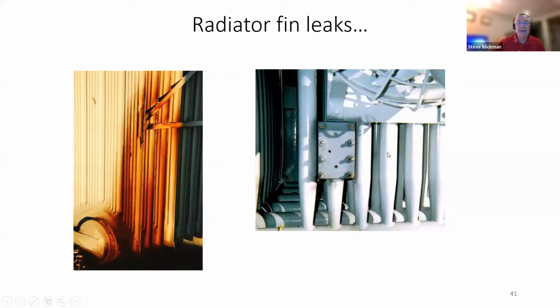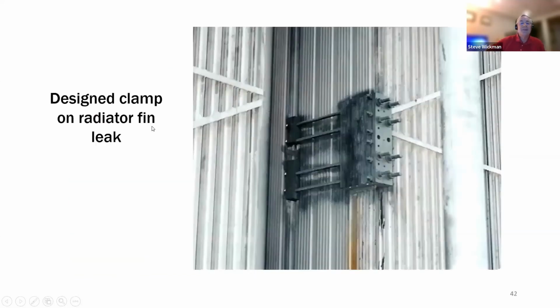So you're looking at this and saying, yeah, great, you're showing a picture of a clamp around a tube. This is a flat fin. How do you fix that? Well, this one merits a full screen photo, which is why I put it separately. But basically, it's a clamp in a C-type configuration, and the threaded rods run to the other side of that fin with just a backing plate to hold it tight up against the fin. And here's a case where this clamp is fairly weathered, so it's been in place for a while, which shows that it has been effectively containing that leak on that radiator fin for quite some time.